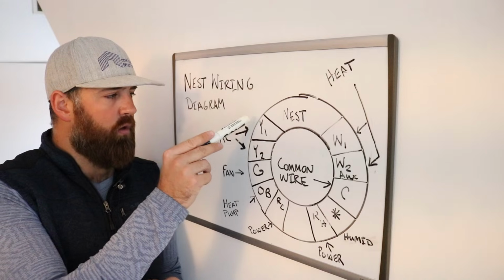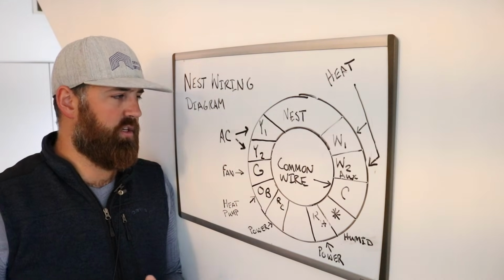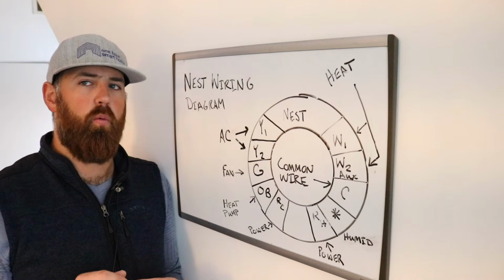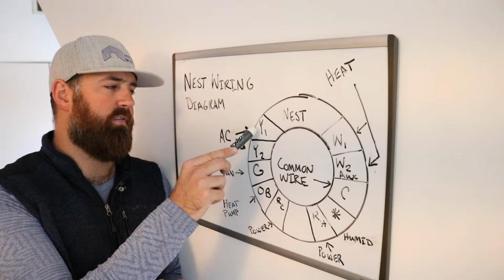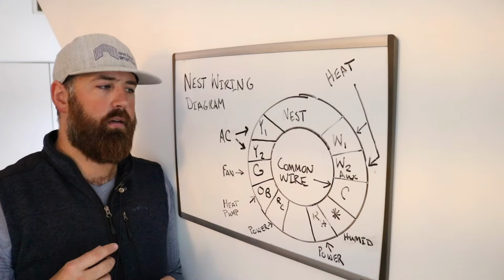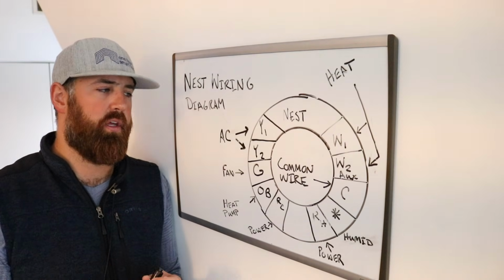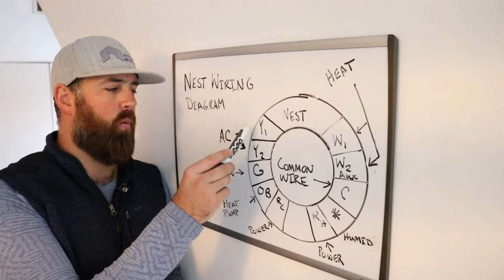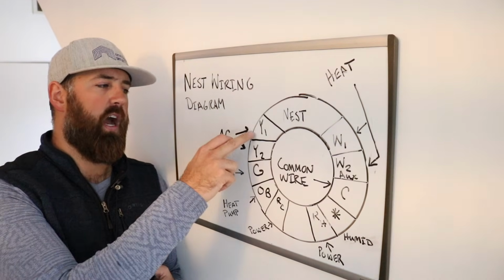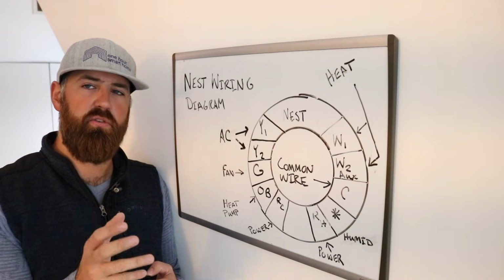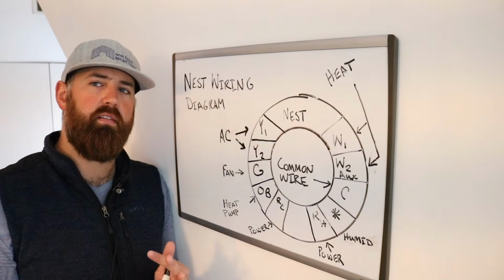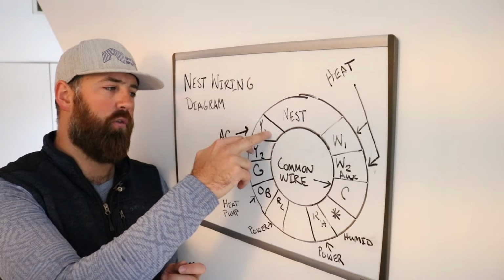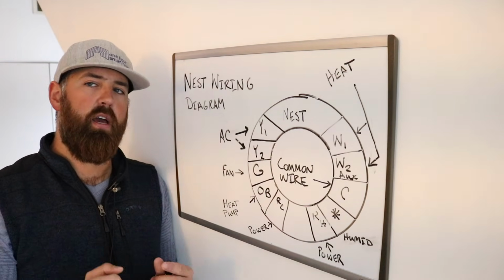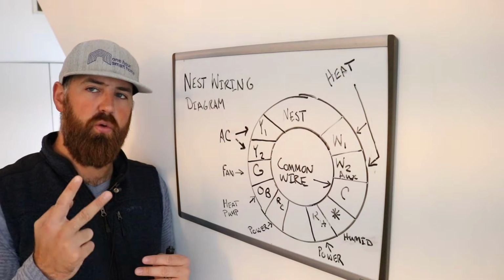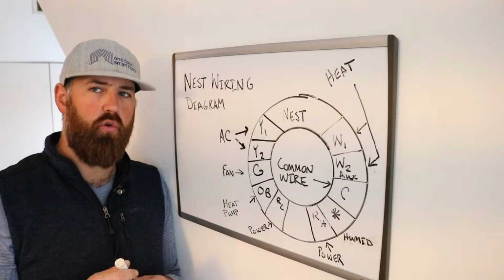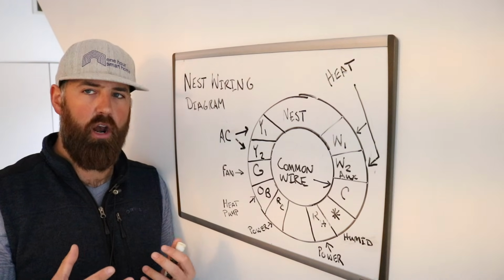Over here we've got Y1 and Y2. In a typical 4-wire system, you would only have Y1 connected. Y is for cooling, air conditioning. The difference between Y1 and Y2 is whether you've got two-stage air conditioning or two-stage cooling. Most people just have single-stage cooling. If on your old thermostat you had both Y1 and Y2 connected, that would mean you had two-stage cooling, which is really just a high and a low for your air conditioning compressor.